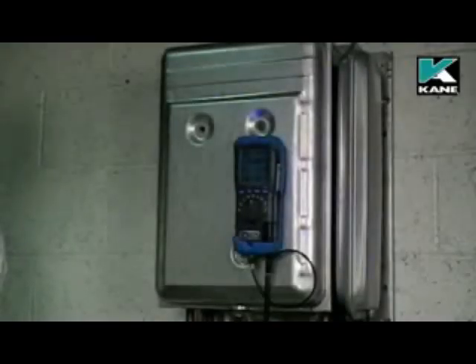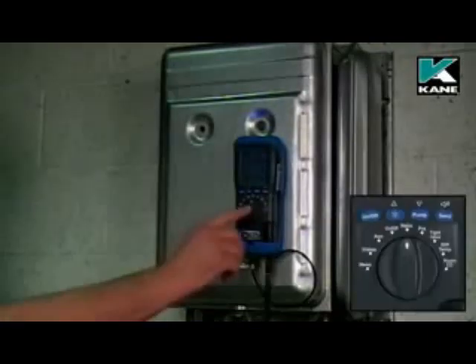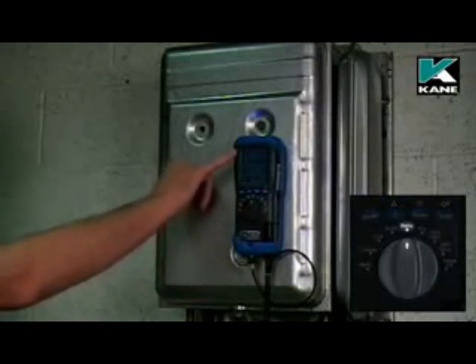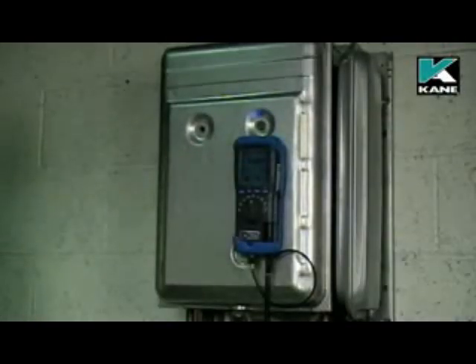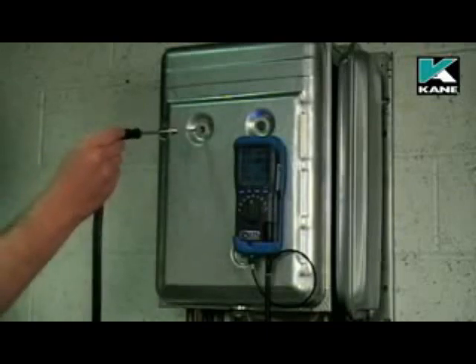When the fresh air purge is complete, move the dial to where it says ratio and check that the fuel is the correct fuel. You can select the fuel via the menu. Having referred to the boiler manufacturer's instructions regarding the position of the probe and also the test procedures, insert the probe into the boiler.